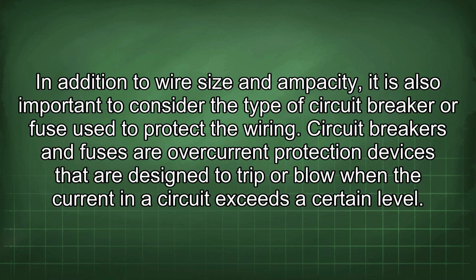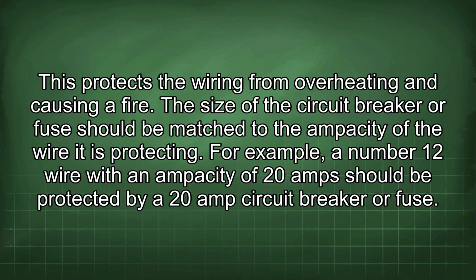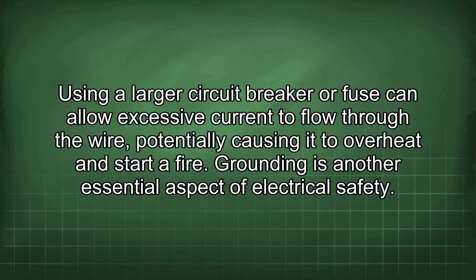In addition to wire size and ampacity, it is also important to consider the type of circuit breaker or fuse used to protect the wiring. Circuit breakers and fuses are overcurrent protection devices that are designed to trip or blow when the current in a circuit exceeds a certain level. This protects the wiring from overheating and causing a fire. The size of the circuit breaker or fuse should be matched to the ampacity of the wire it is protecting. For example, a number 12 wire with an ampacity of 20 amps should be protected by a 20 amp circuit breaker or fuse. Using a larger circuit breaker or fuse can allow excessive current to flow through the wire, potentially causing it to overheat and start a fire.